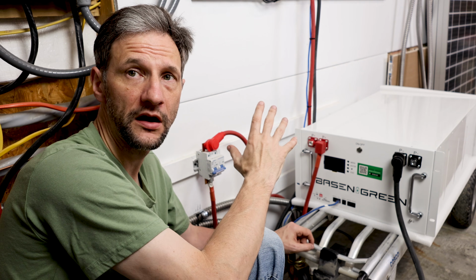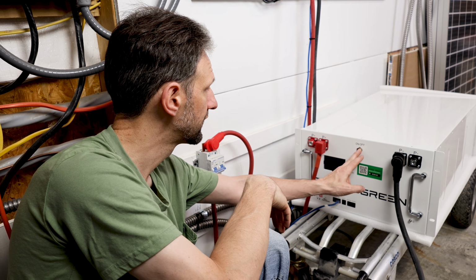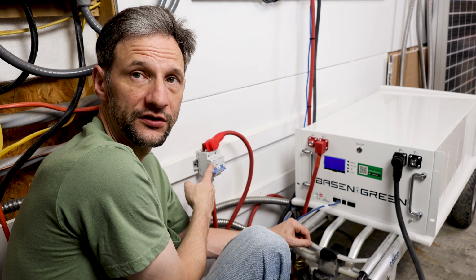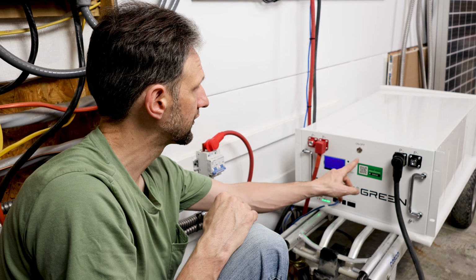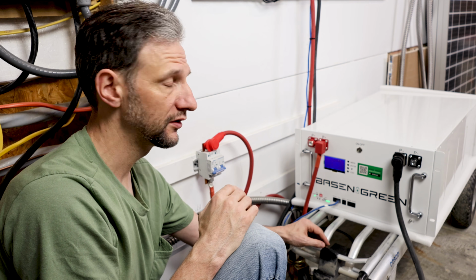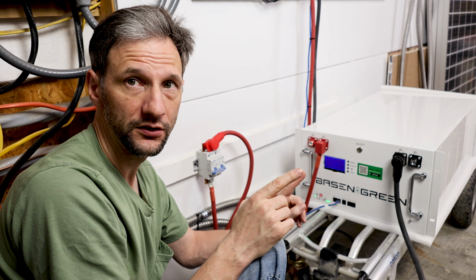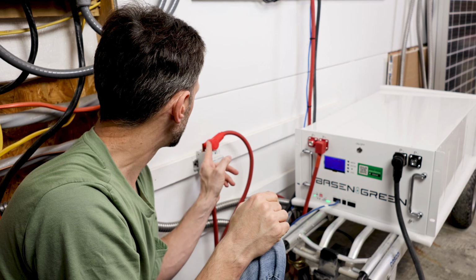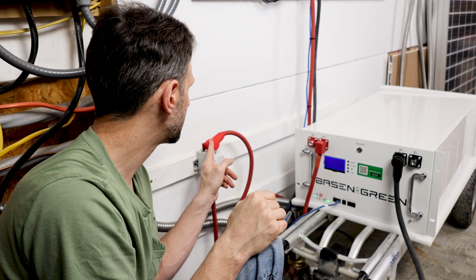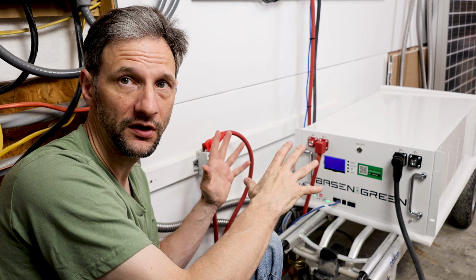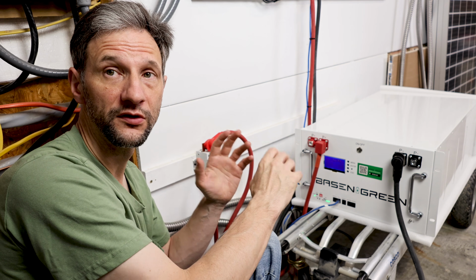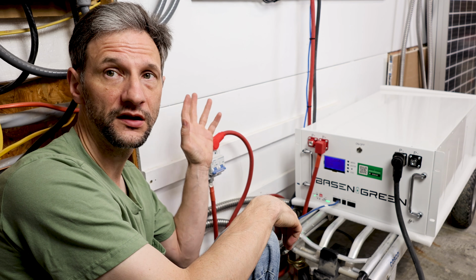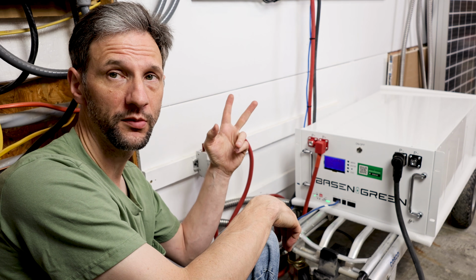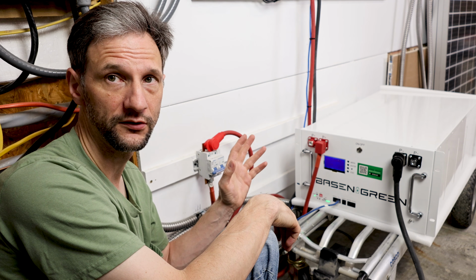Now I can power up the inverter and the BMS. We're still not actually connected, but that will allow us to confirm communication with the inverter. As a little trick I mentioned before, I'll show you that the voltage between the positive and negative is actually around 50 volts from the inverter side. That's because with Victron inverters, if you have them connected to grid power, they will pre-charge the capacitor for you, so you won't need a pre-charge resistor at all.